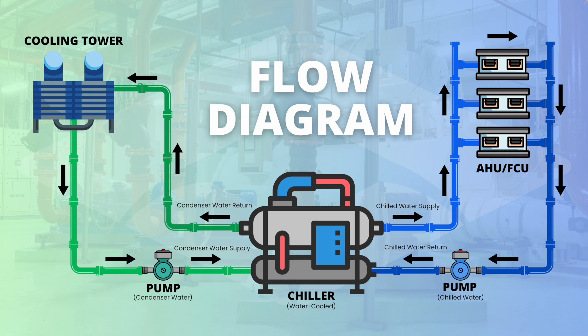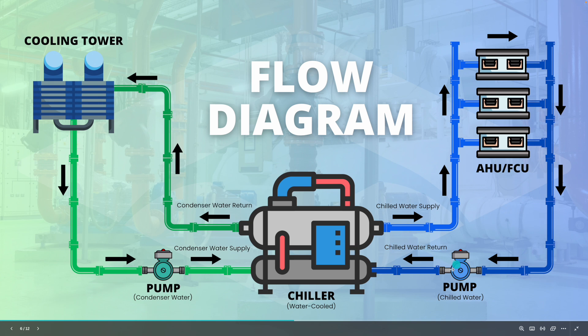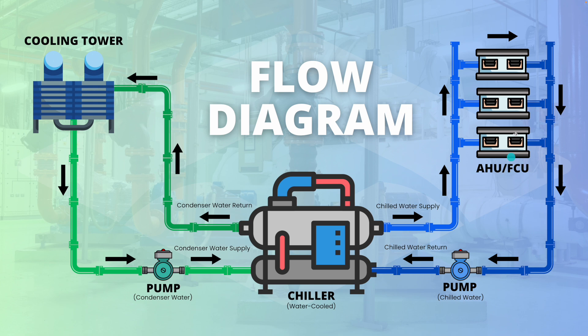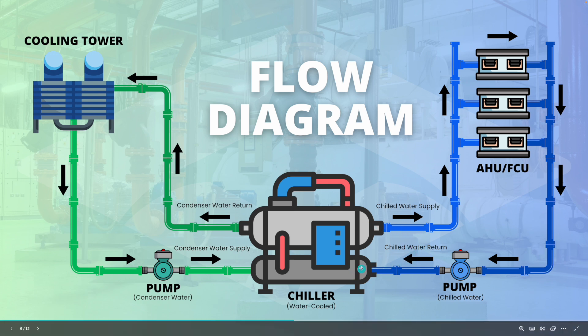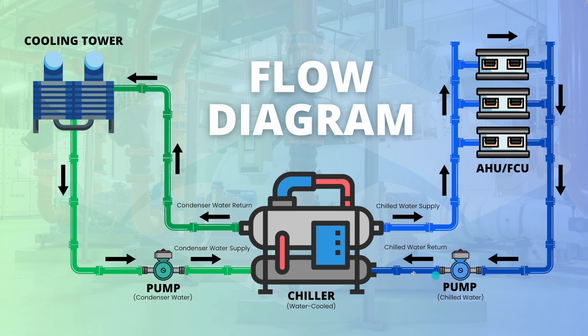Now let's look at how these four components work together using the flow diagram. At the center is the chiller — this is the water-cooled type — with the chilled water pump, condenser water pump, AHU and FCU, and cooling tower. The chiller first produces chilled water supply, which goes directly to the AHU and FCU. The chilled water passes through their cooling coils, where air is drawn across the coil and cooled down. The supply is typically 6 to 7 degrees Celsius and the return is about 12 degrees Celsius — a 5-degree temperature difference. The pump circulates the chilled water, which then returns through the evaporator of the chiller and continues the cycle in a closed loop.